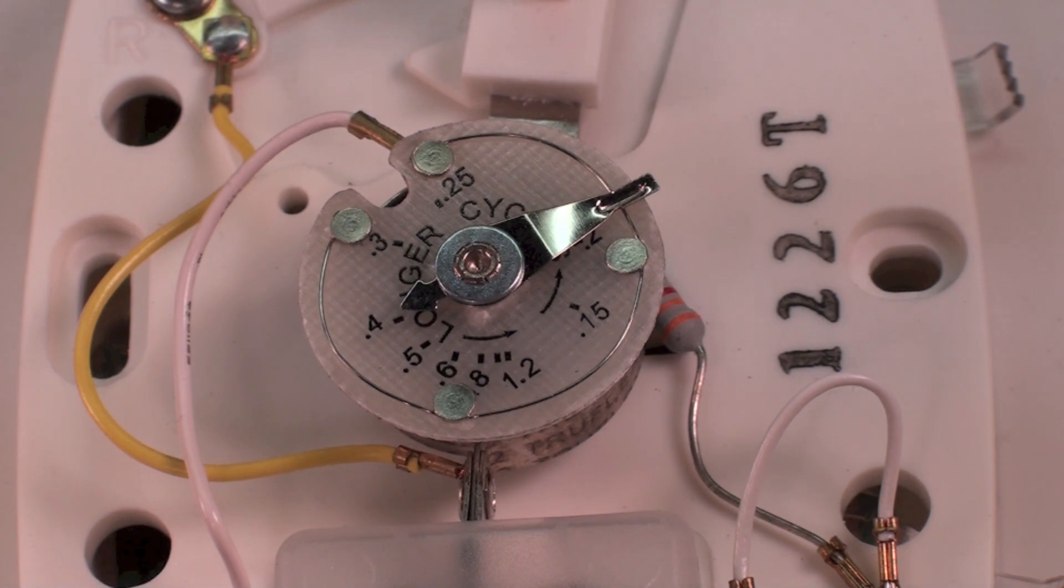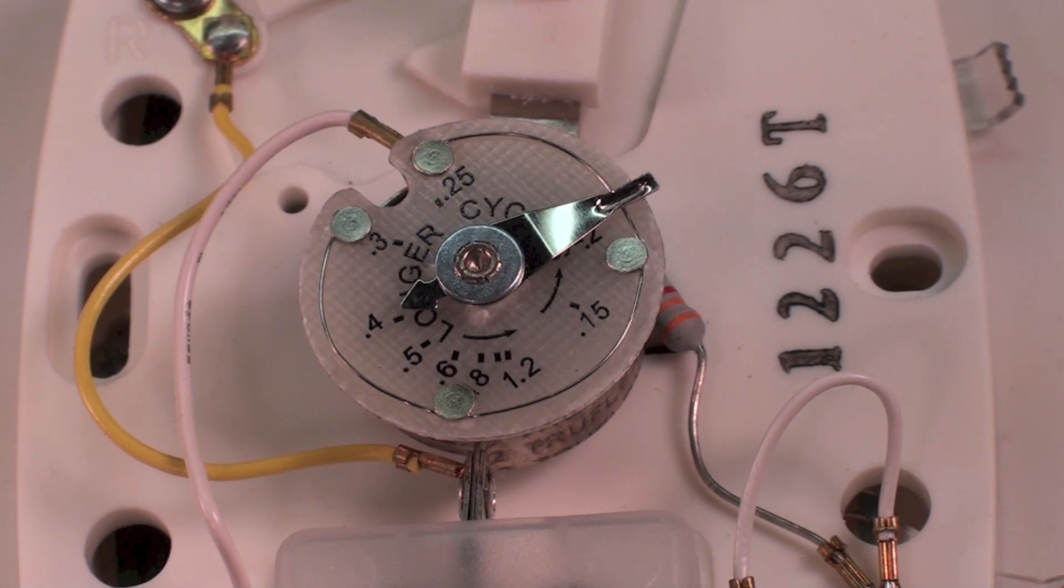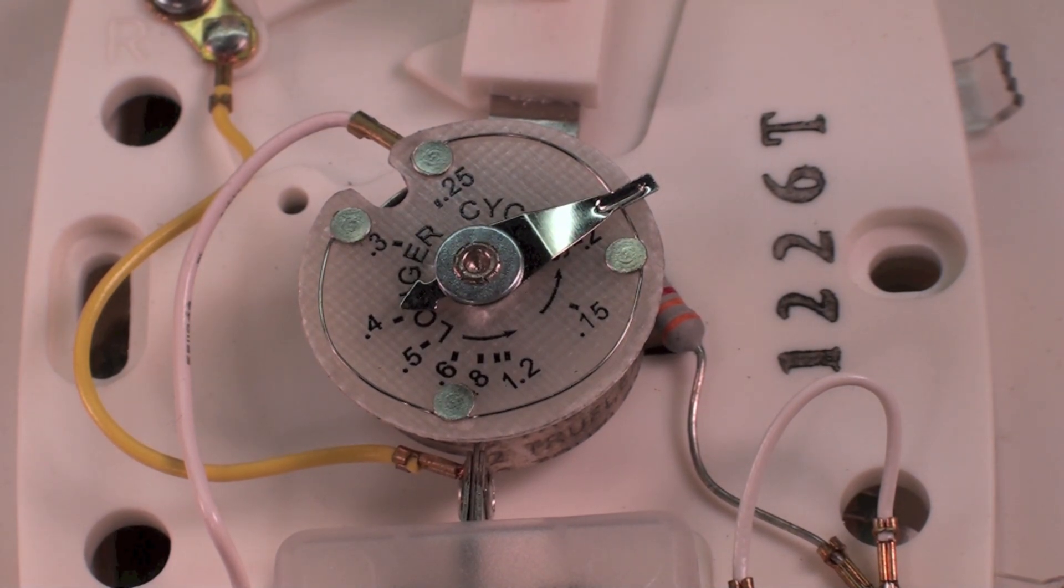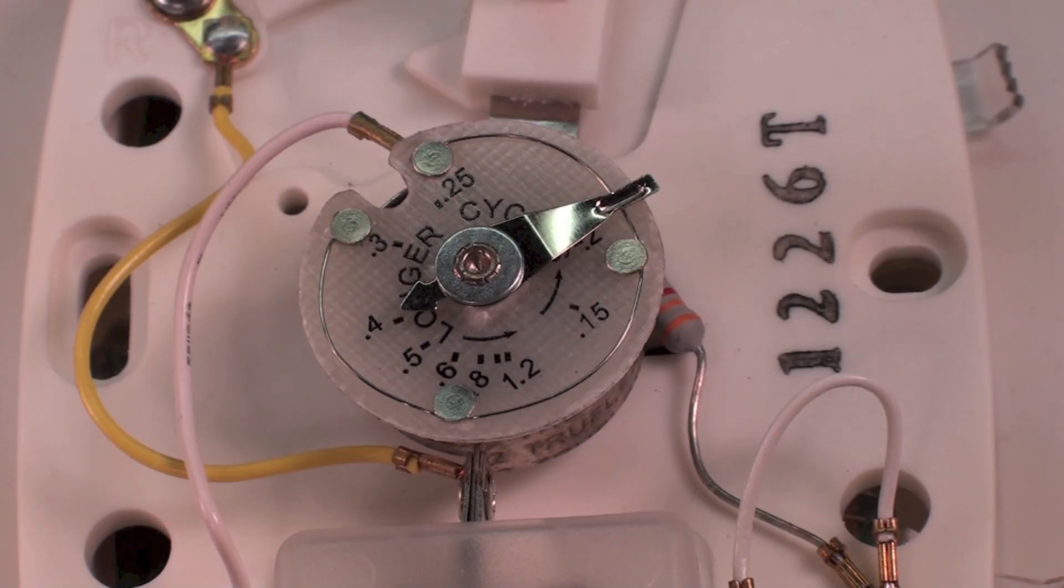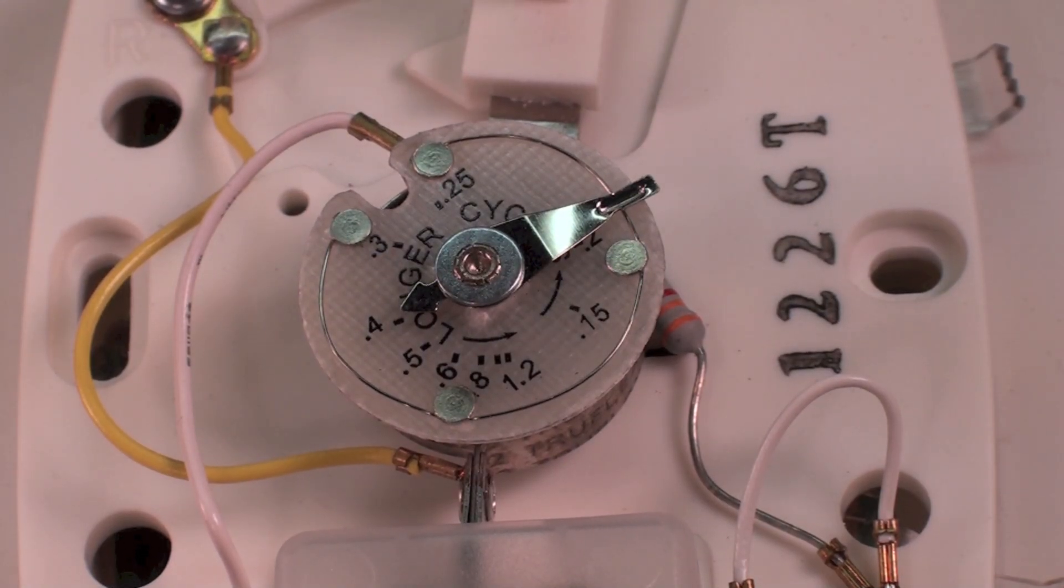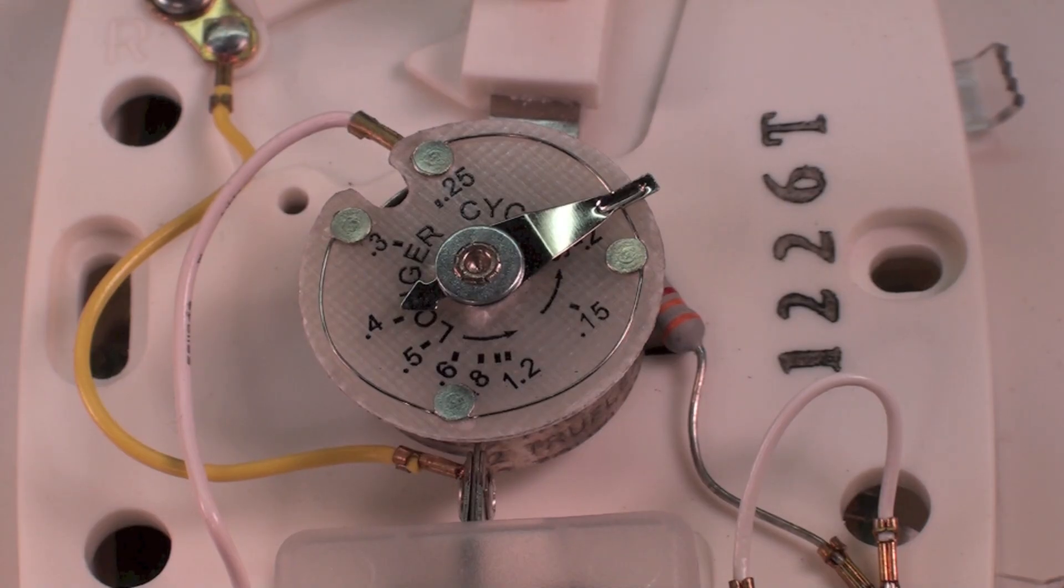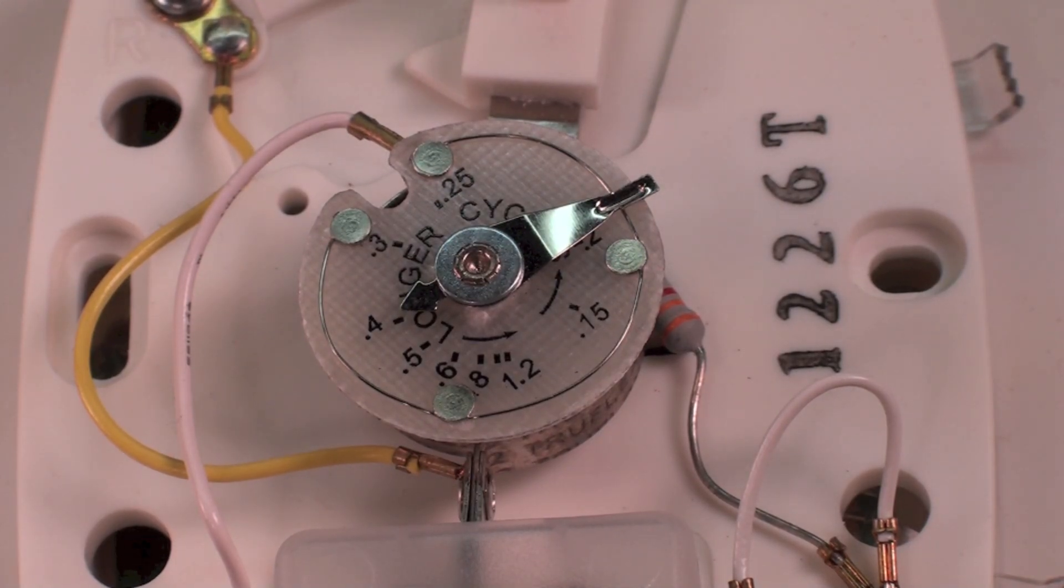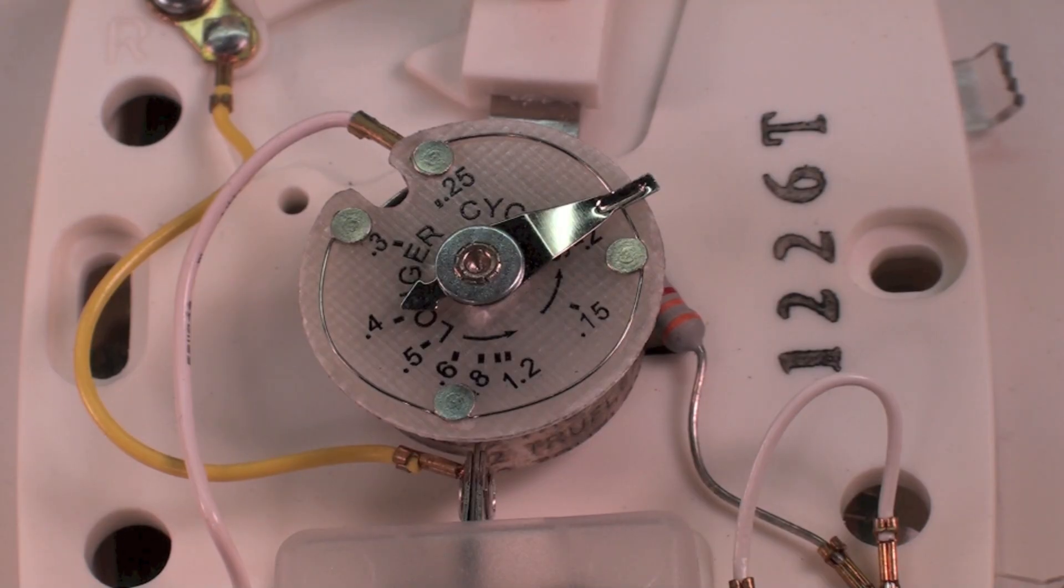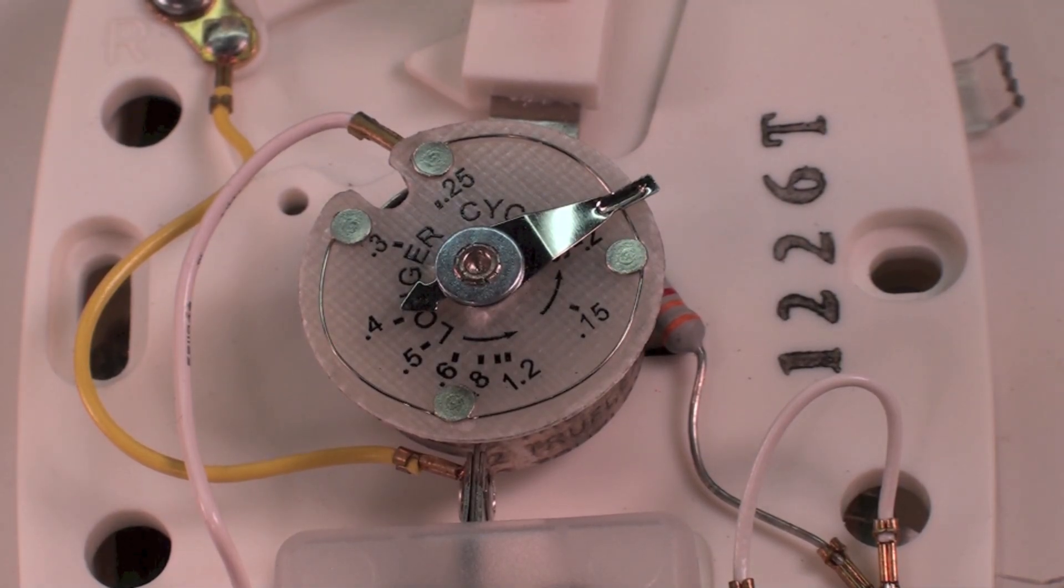Other things that can affect this - if the cycles are too long, the thermostat may not be the problem. It could be that something is blocking the registers, preventing air from moving throughout the house. Could be the thermostat is located incorrectly where it's in a dead airspace.